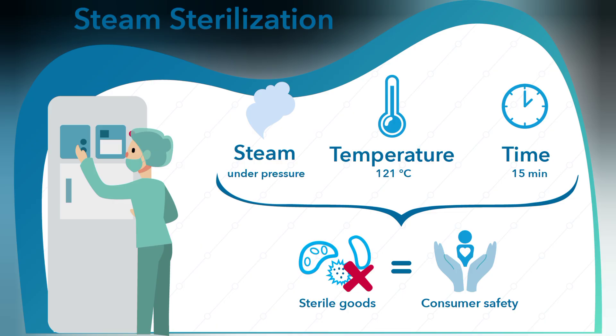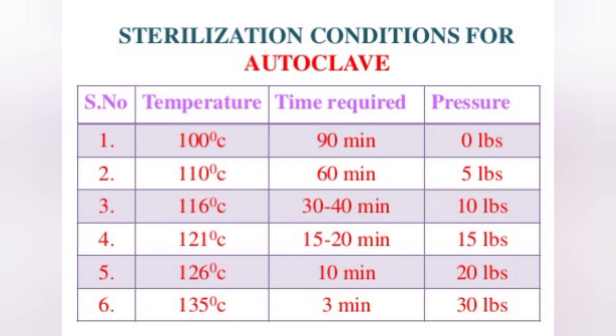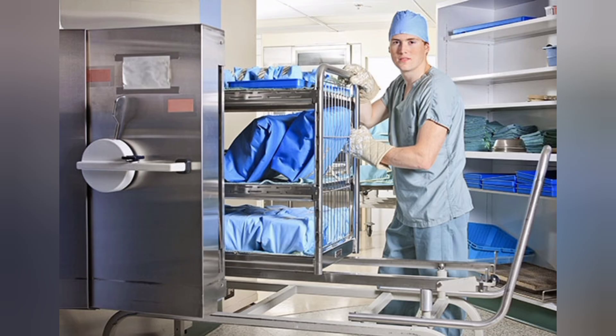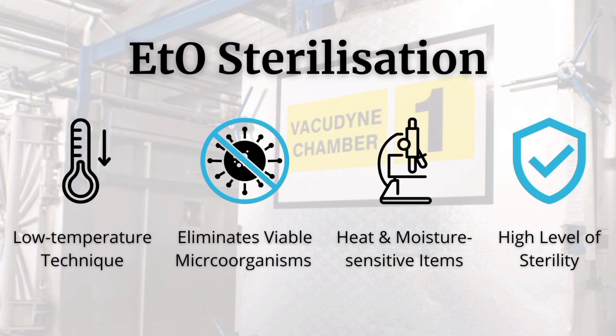For different kinds of goods, different types of sterilization techniques are used. The first type is steam sterilization. It destroys microorganisms, and this process is enhanced by the addition of moisture. Steam alone is not sufficient; pressure greater than atmospheric is applied to steam, which increases the temperature for thermal destruction of microbial life. No living thing can survive direct exposure to saturated steam at 120°C for longer than 15 minutes, or at 134°C for longer than 4 to 7 minutes. As temperature and moisture increase, exposure time may decrease, and it may vary according to the type and size of the load. At the end of the cycle, re-evaporation of water condensate must effectively dry the contents to maintain sterility.